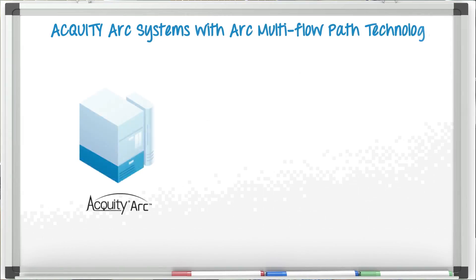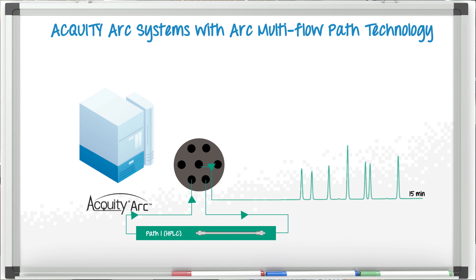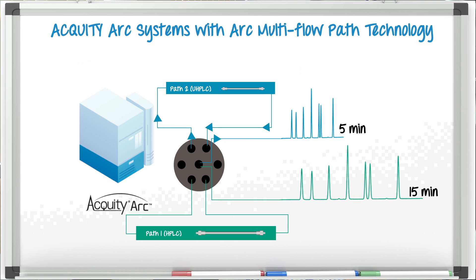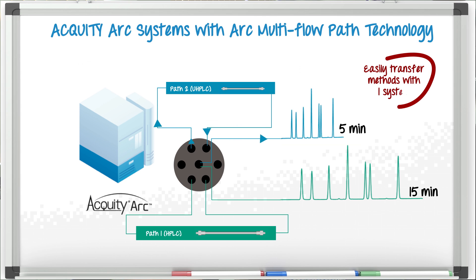The ACQUITY Arc System with Arc multi-flow path technology was designed specifically to enable analysts to successfully transfer their established HPLC methods onto a modern LC platform while still providing the flexibility to further improve productivity in the future. By simply selecting between one of the two fluidic paths in the system software, the user can reproduce the results created on their legacy HPLC systems. Alternatively, a second fluidic path can be selected to improve performance by scaling that method with a more modern 2.7 micron UHPLC column. This novel technology essentially provides a selectable dwell volume to easily enable the transfer of LC methods from any commercial LC system, mitigating the need to revalidate the assay by emulating both the dwell volume as well as the behavior of how these mobile phases are mixed.